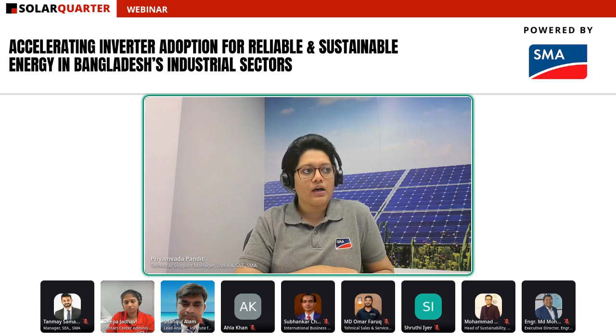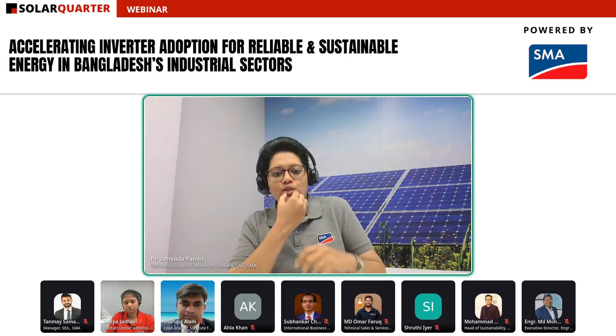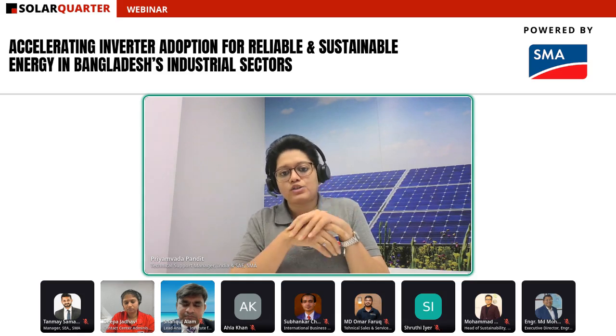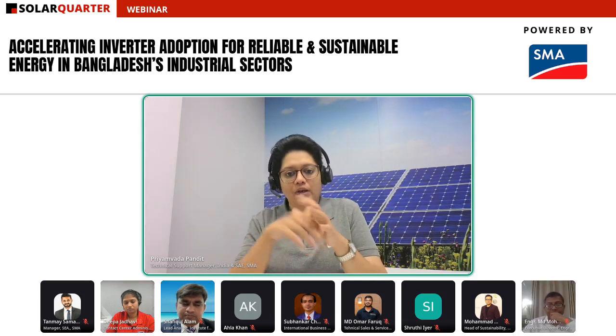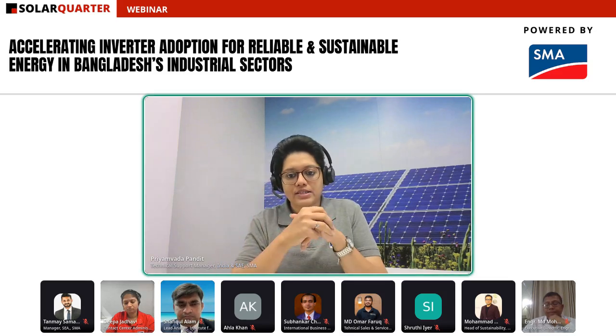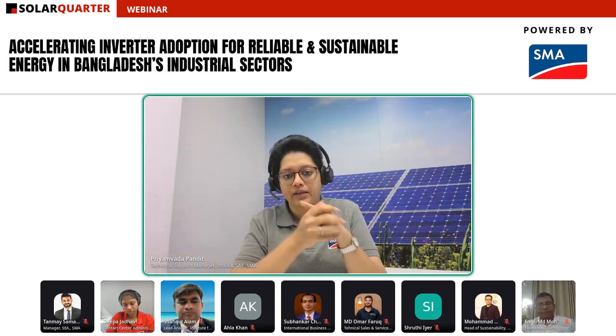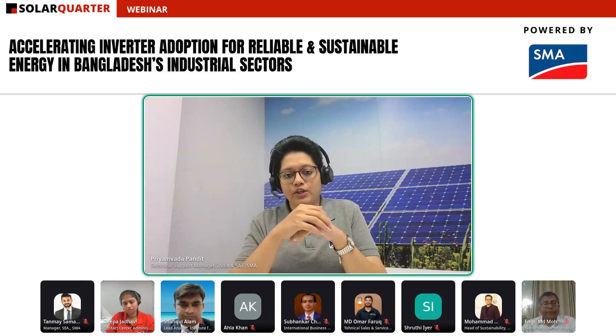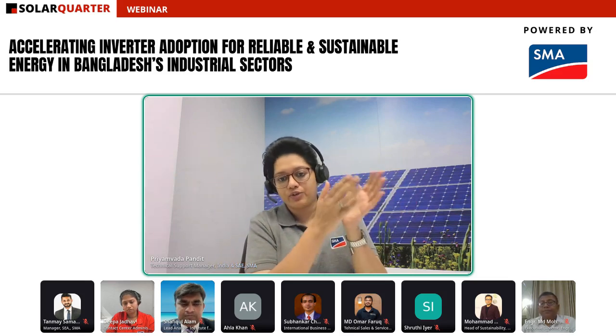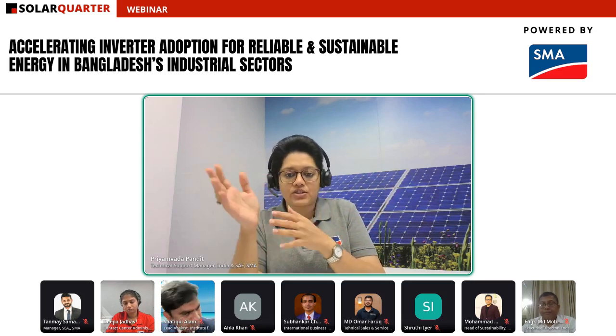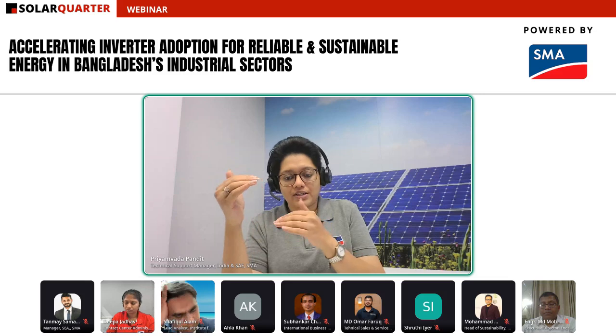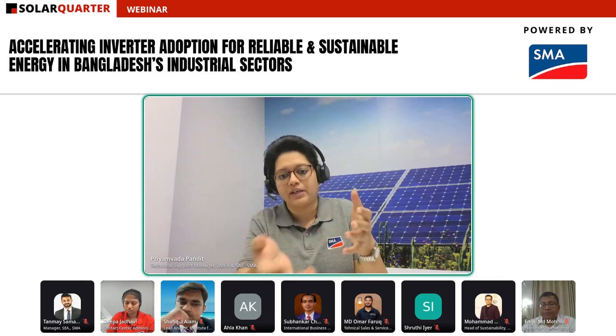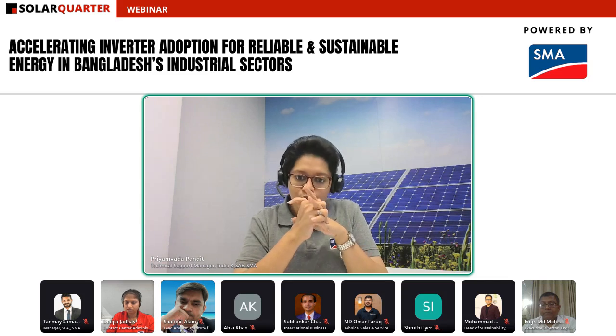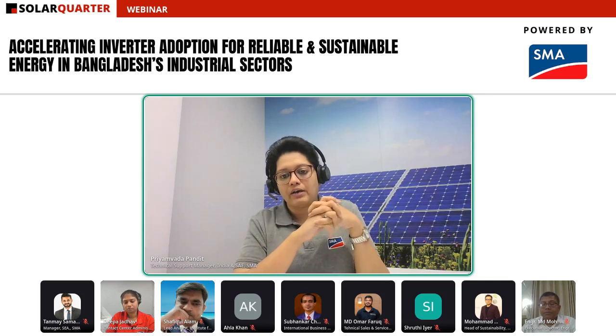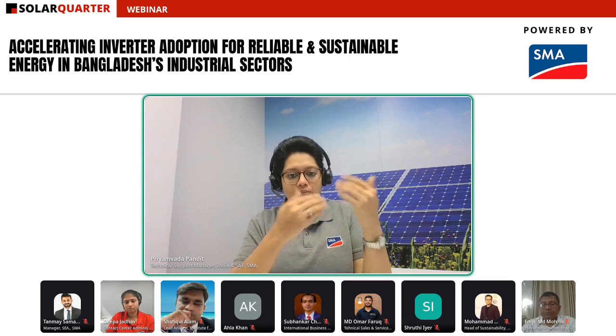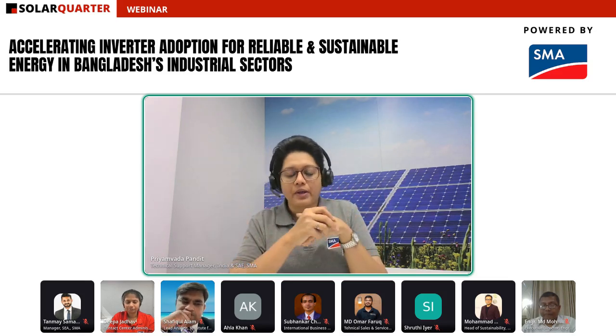At the same time, in the industries where you are using, say, diesel generators, it is also possible. If you want to integrate your system along with the grid, there are probably multiple reasons. Some of the factors require 24/7 uninterrupted energy, and if the grid is not stable enough, then some of the processes run purely 24/7 on the diesel generators. In some of the industries, diesel generators will act as a backup. But in both cases, if there is significant use of diesel generators, you would want the PV to be integrated with those systems. So that is also possible. For many years, this is not a new solution. We have solutions, there are controllers, which allow you to have this integration. This is one thing.